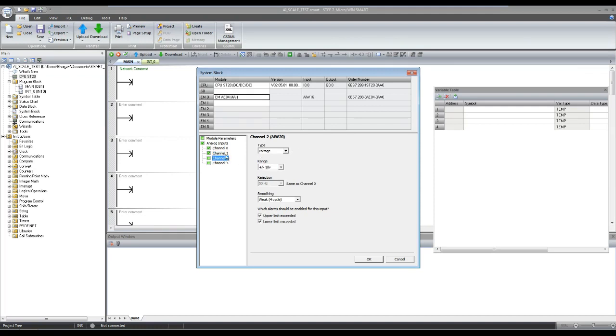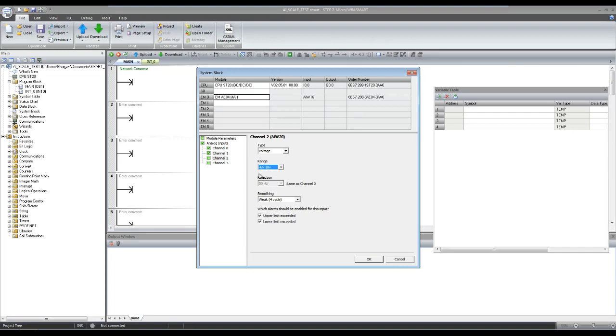And let's configure channel 2 as voltage input and range as 0 to 10 volts DC. Similarly, if channel 2 is selected as voltage input, then channel 3 can be used with voltage signal only. But here different voltage level can be selected if required.